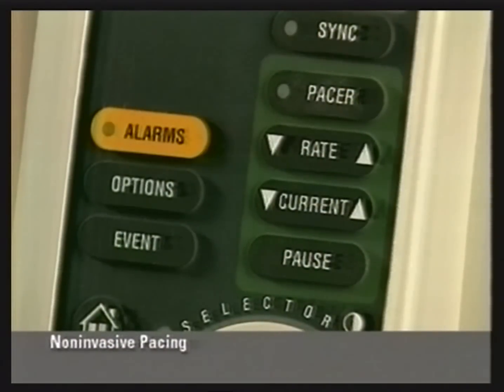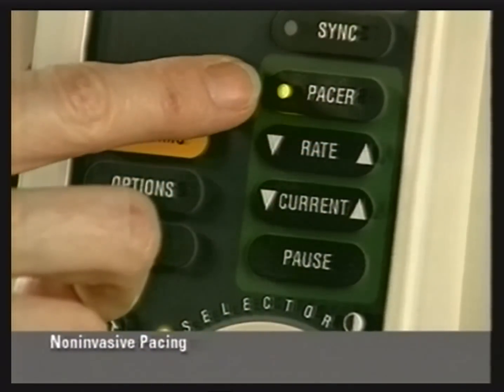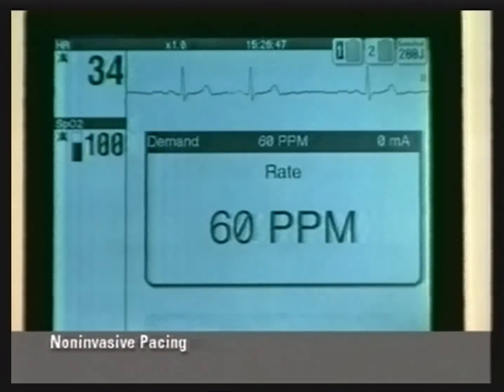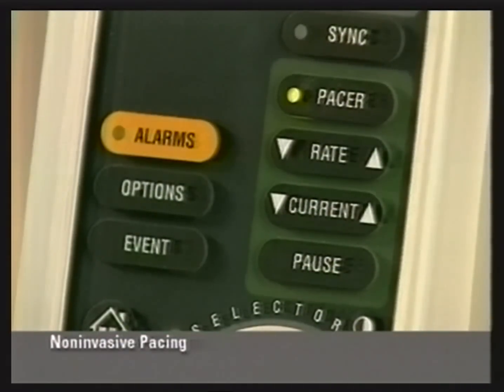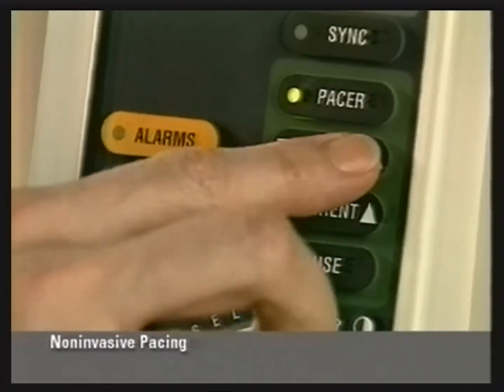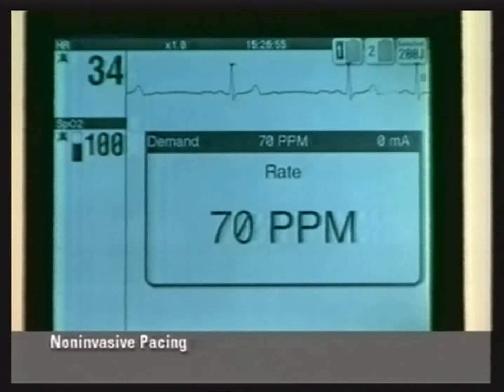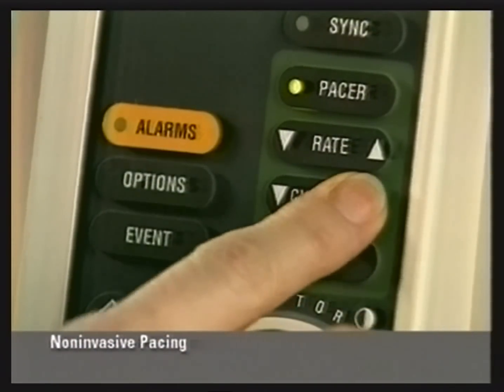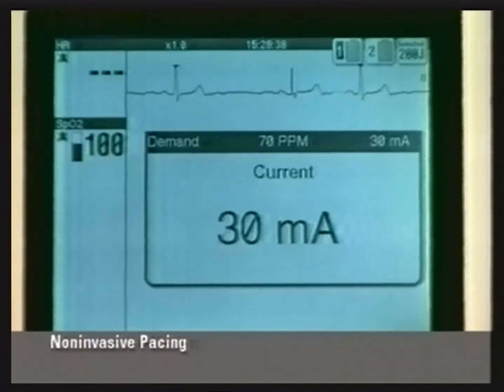Press pacer. Confirm that the LED lights and that the sense markers appear and are properly positioned on the patient's beats. The demand pacing menu also appears. Select the desired pacing rate by pressing the rate button or rotating the selector. Increase current by pressing the current button or rotating the selector. Slowly increase the current until electrical capture is achieved.